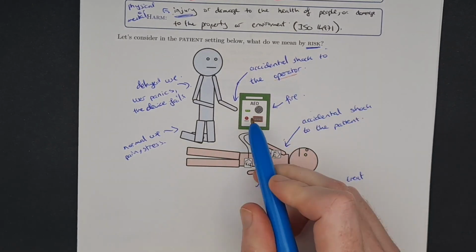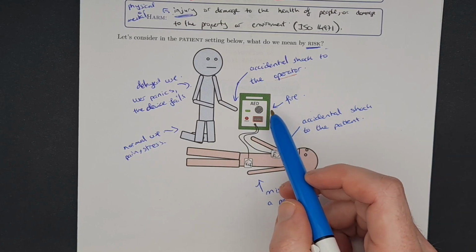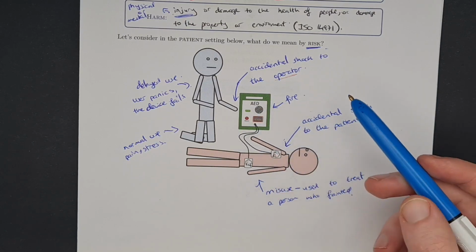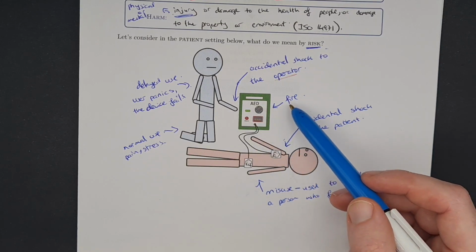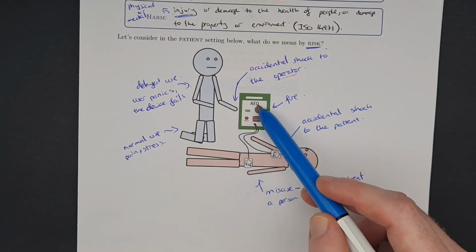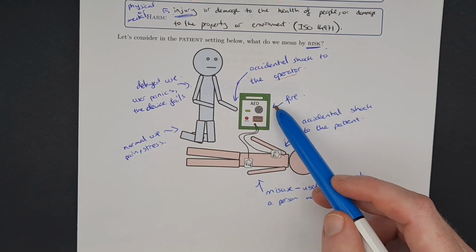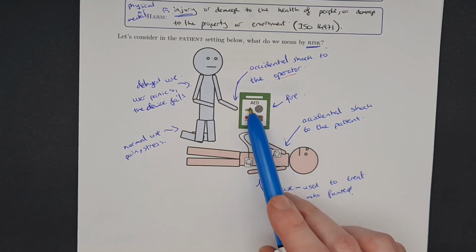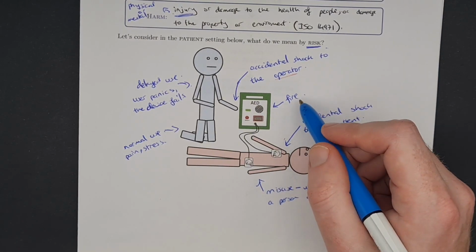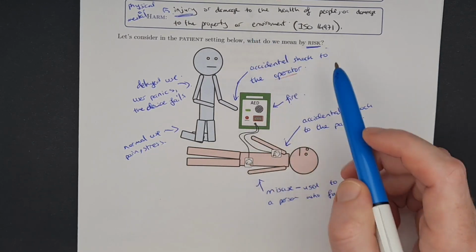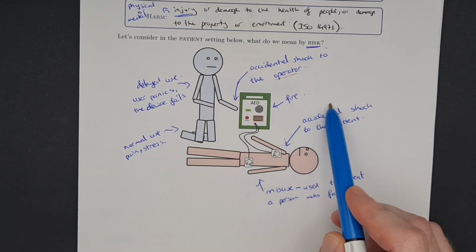And of course, another one that we might consider, I'll put it here, there's a fire risk. And that's because this device is an electronic device inside a mechanical assembly. That mechanical assembly is likely going to be made of plastic. So it is reasonably foreseeable that the internal electronics, some failure could result in a fire and then the plastic case goes on fire, especially when you consider a defibrillator has hazardous voltages inside it. And you could get stuff like arcing. Then, of course, we're going to see fire as a risk, and that will be a risk to the environment. So these we can all consider our risks.